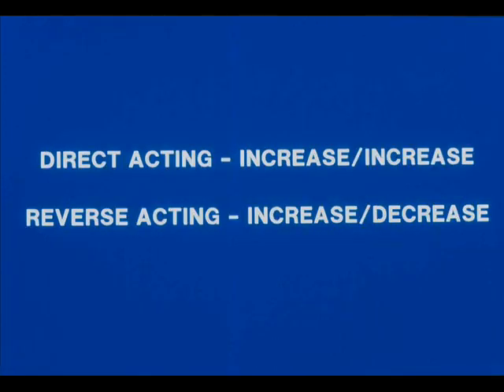Remember the difference between a direct and reverse acting positioner. Direct acting means an increasing input signal produces an increase in output. Reverse acting means an increasing input signal produces a decrease in output.